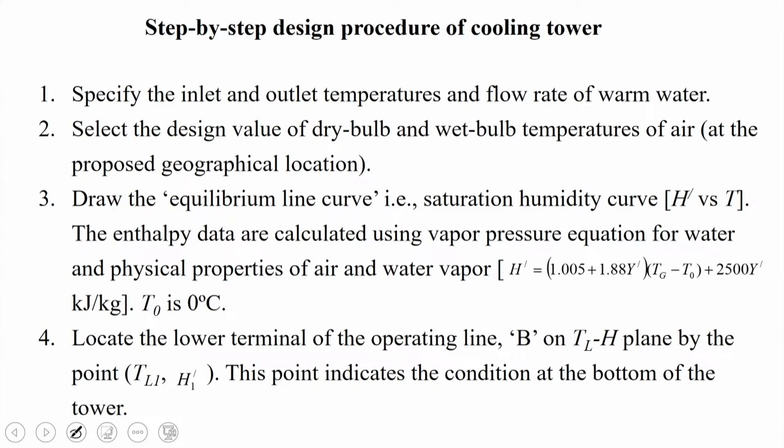The third step is to draw the equilibrium line curve, that is the saturation humidity curve, which is H' versus temperature. The enthalpy data are calculated using the vapour pressure equation and physical properties of air and water vapour: H' = (1.005 + 1.88·Y') × (Tg − T0) + 2500·Y', in kJ/kg, where the reference temperature T0 is taken as 0°C.